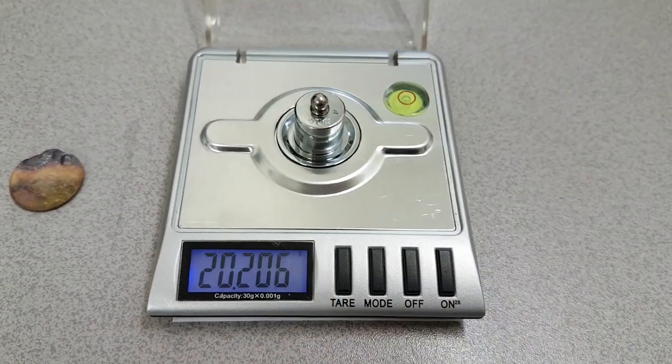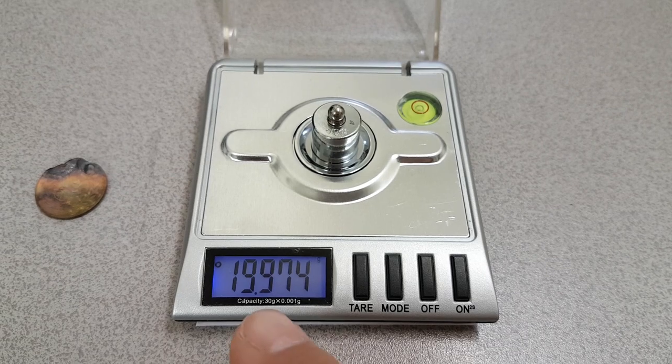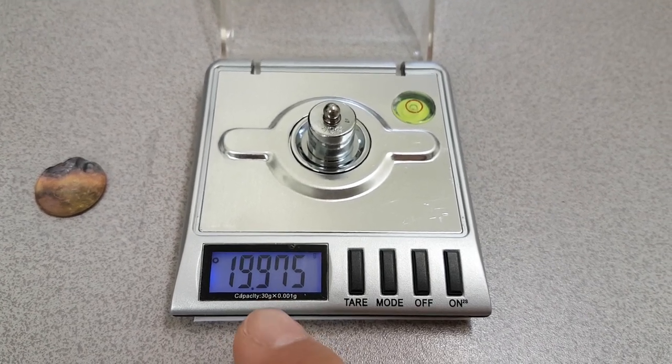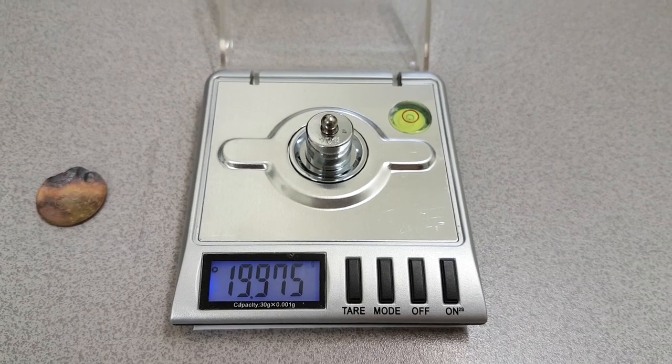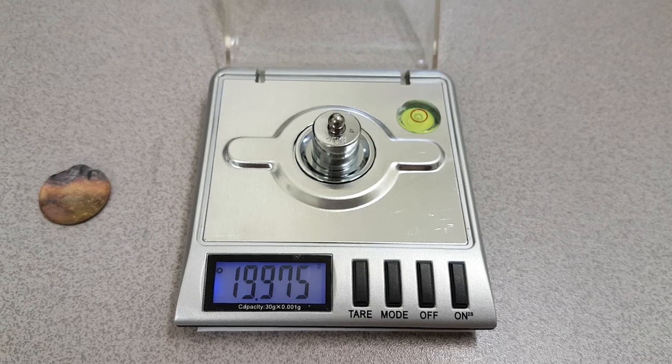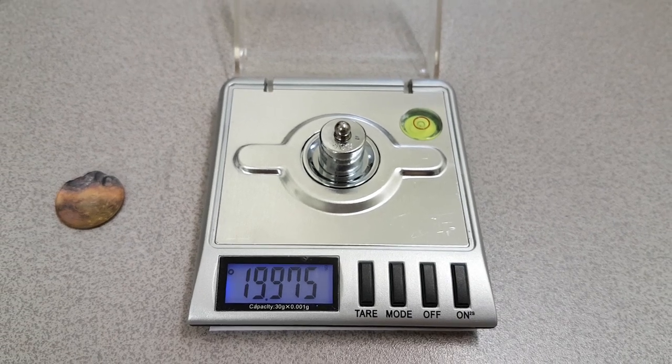Okay, so that's in the middle there. Over 20 grams, we're seeing 0.025 of a gram discrepancy here. It's slightly under-measuring the weight.